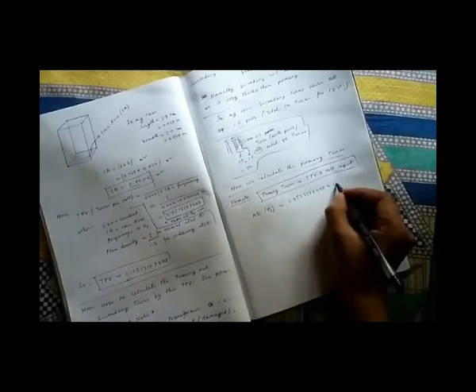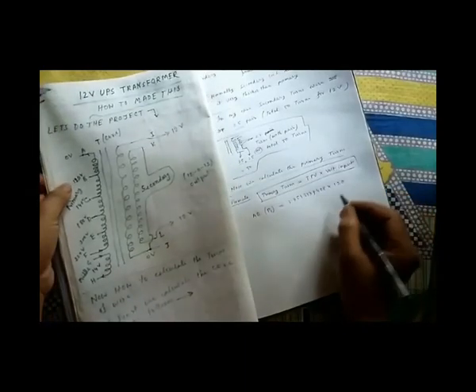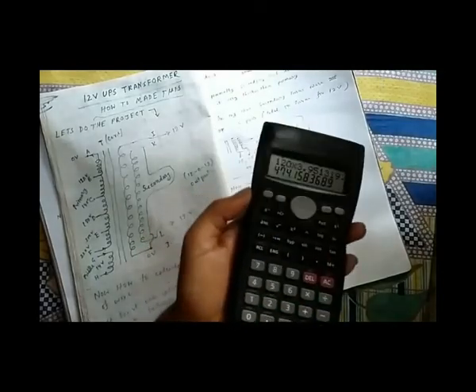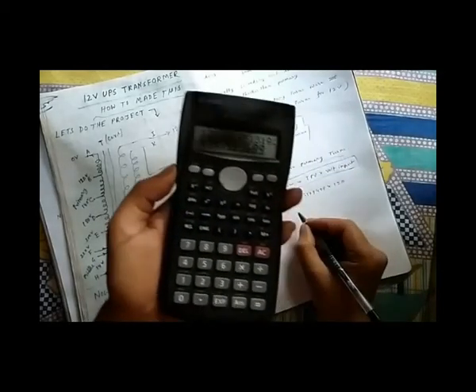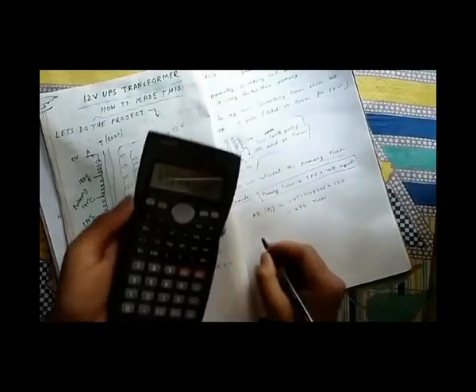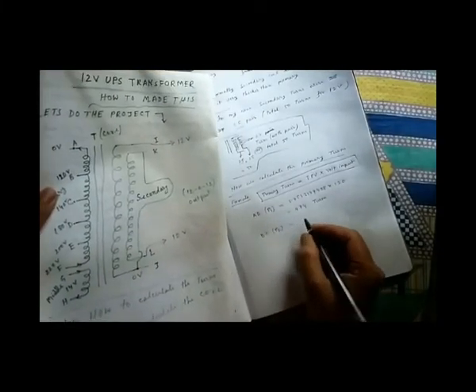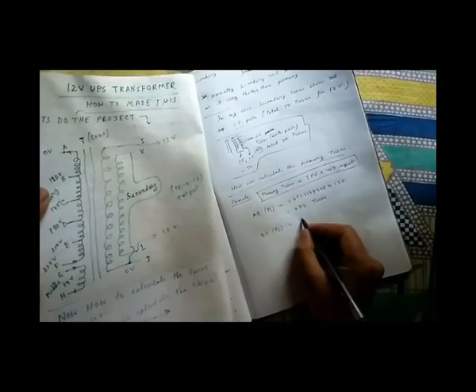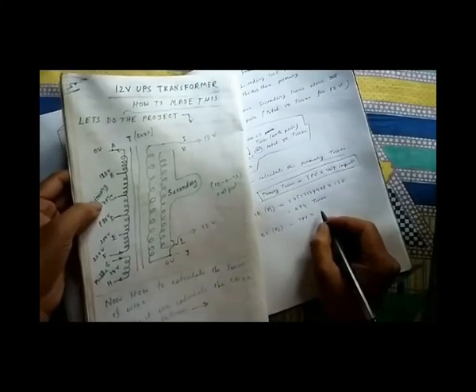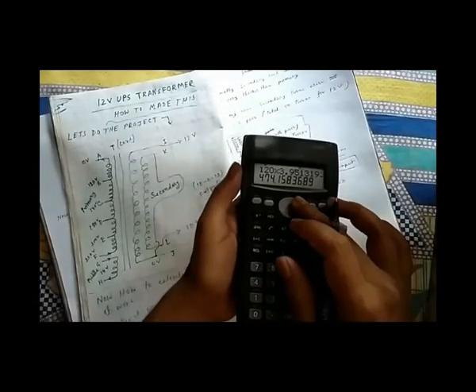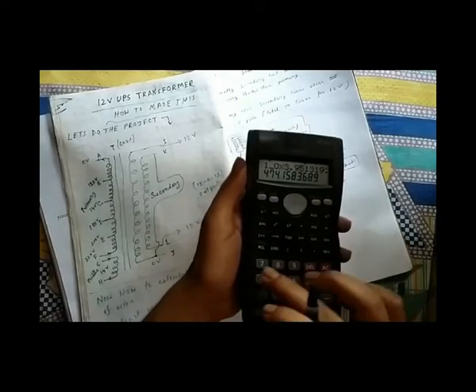Primary turns is equal to TPV into input voltage. For the first point A B point 1, the primary turns will be TPV into 120 volt, and result becomes 474 turns. And for the second point B C point 2, the primary turns will be TPV into 140 volt, and result becomes 553 turns.